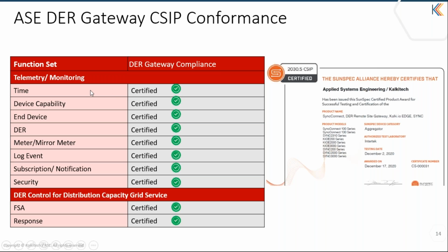For telemetry, all the functions as defined in the 2030.5 and CSIP, time, device capability, mirror usage points, log events, subscription, security, all the mandatory function sets as per the 2030.5 CSIP standard have been validated for the telemetry purpose as well as for the control purpose. For example, the function set assignment as well as the response function set has been certified as part of this exercise.